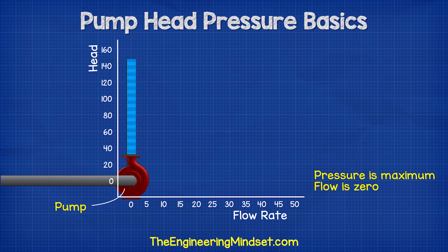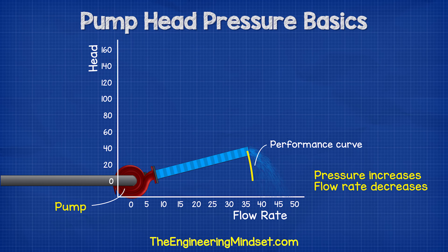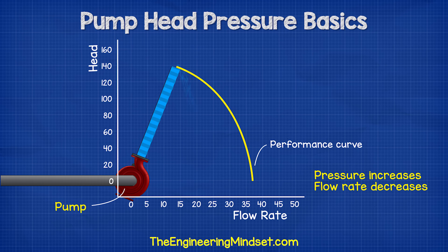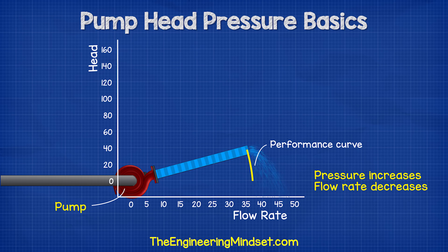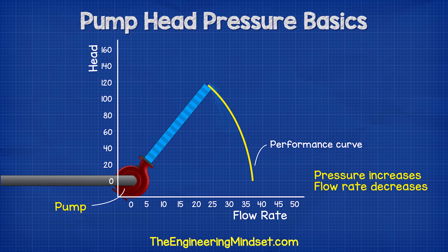At this point it's just spinning the same bit of water, which isn't good for the pump, so you don't want to run a pump like this in the real world. By recording the values during the elevation, we basically get our pump curve, although pump manufacturers don't test pumps this way because it's just not practical.